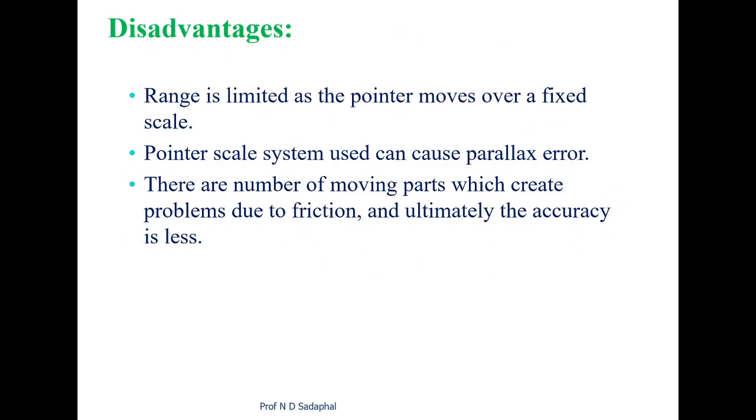Some disadvantages are there. The range which we are measuring is limited, because whenever the pointer is moving it has some limitation, so we cannot read more deviation. Then whenever we are seeing the readings, a parallax error can occur in the measurement. There are also a number of moving parts. They may face the problem of friction while moving, so there might be an accuracy problem in the measurement.